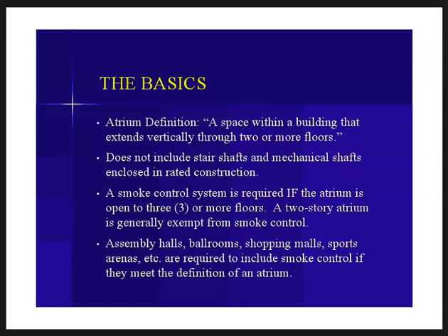But we're going to, for sure, require a smoke control system if the atrium is open to three or more floors. We might, in a two-story atrium, require it, like in a mall or in an amusement building. If you're on Pirates of the Caribbean, well, technically that's 2 stories. I don't know if you realize that. It's a 2-story building that it's encased in. But it's a place with extreme evacuation challenges, an amusement ride. So we're going to require it there, even though it's only 2 stories.